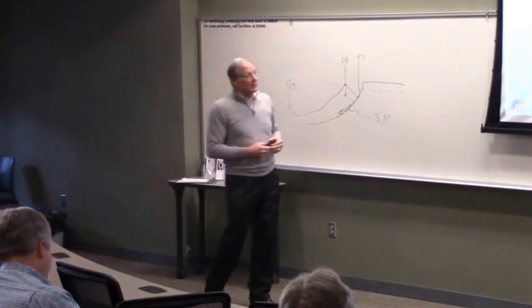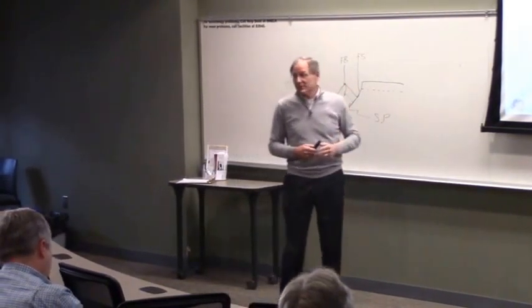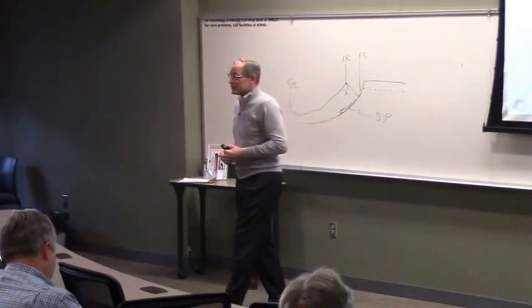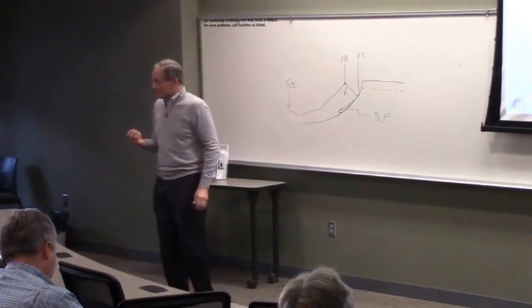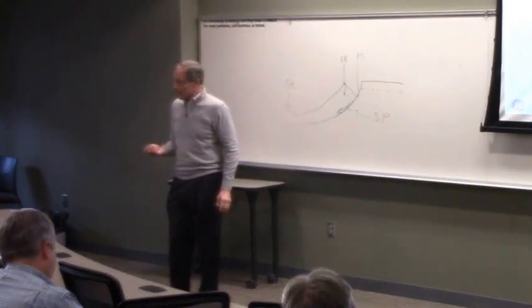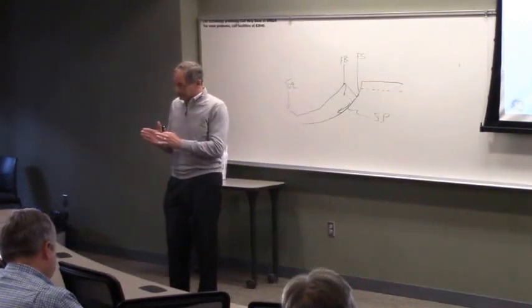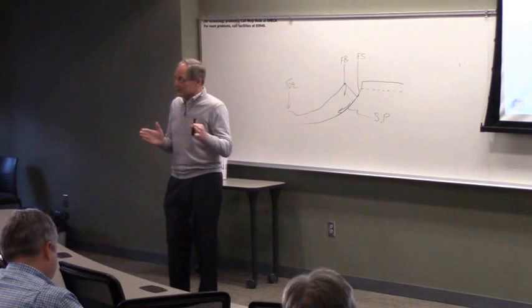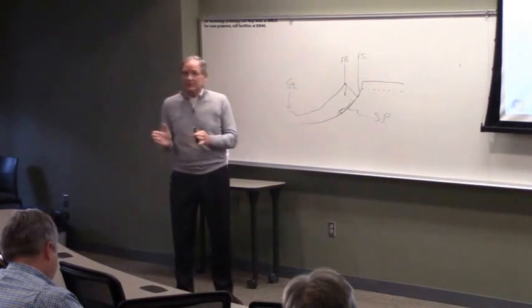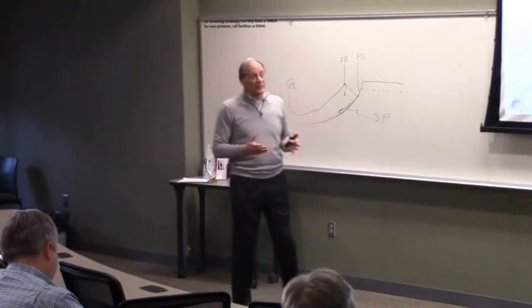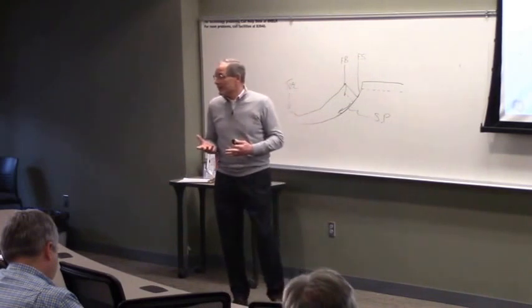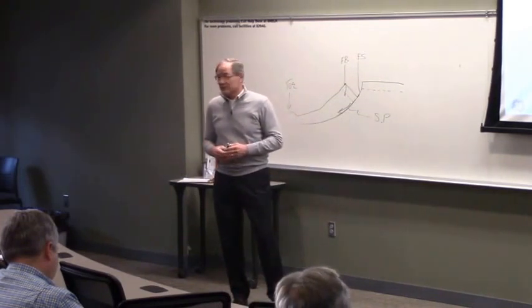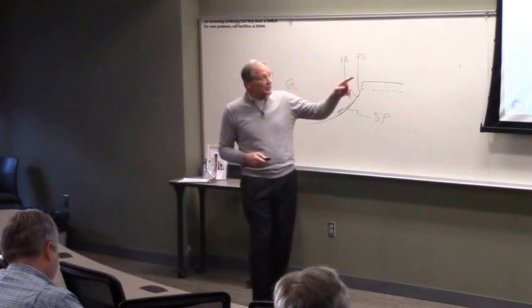One of the goals, particularly in distribution, with fault detection, isolation, and restoration, is to detect the fault quickly, locate it, isolate it, then restore service upstream and downstream of the faulted section. If we can do that without a human in the loop, we can get it done in a minute or two. And then next is resiliency.